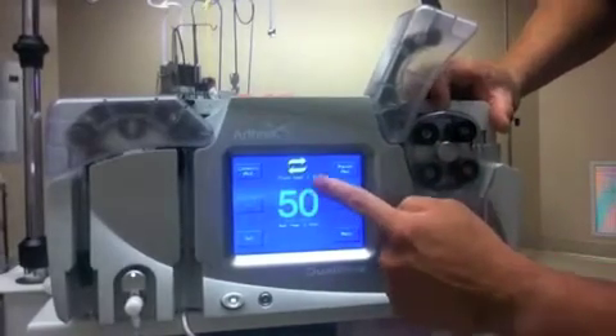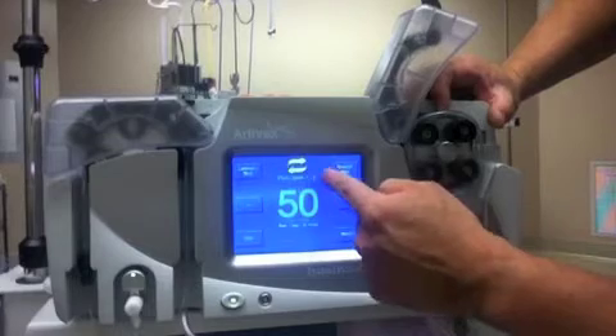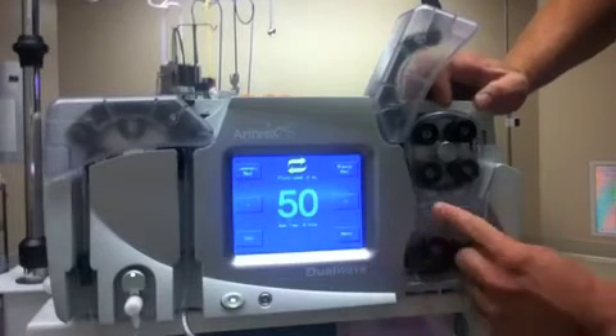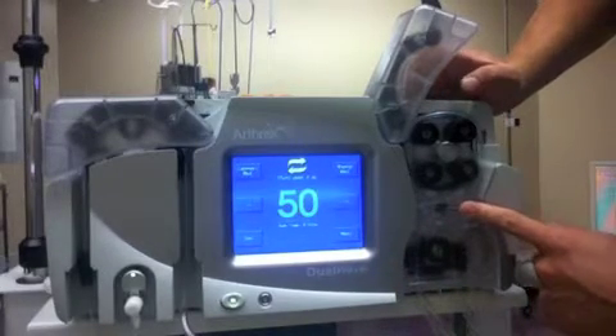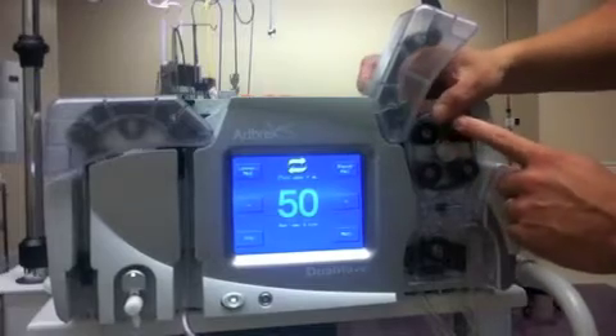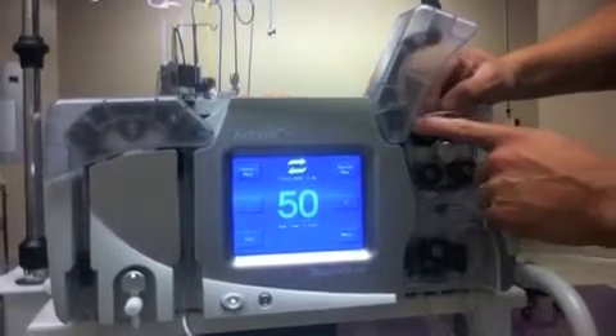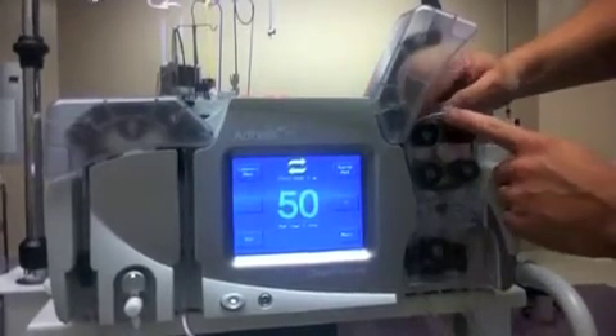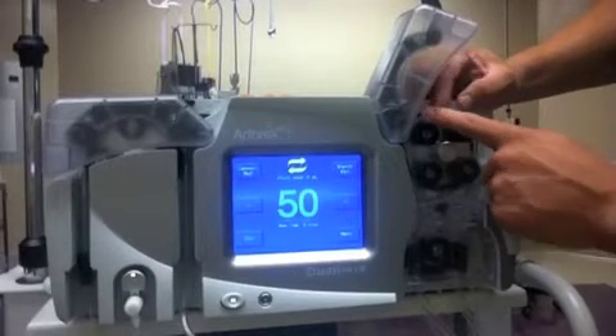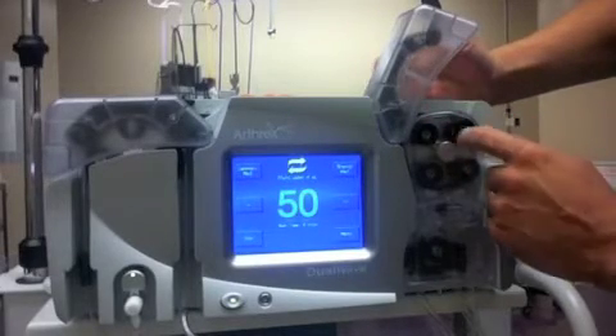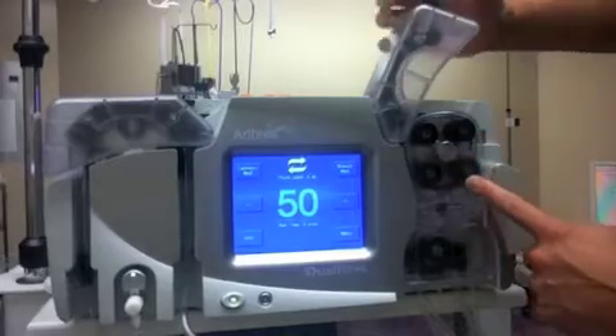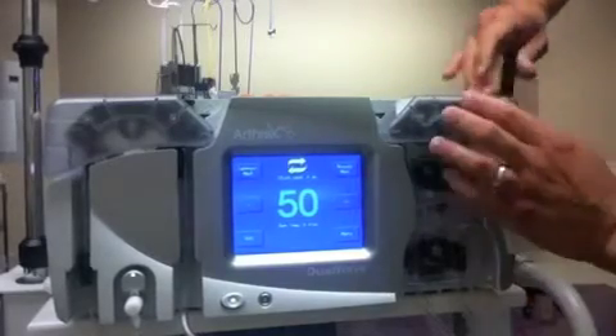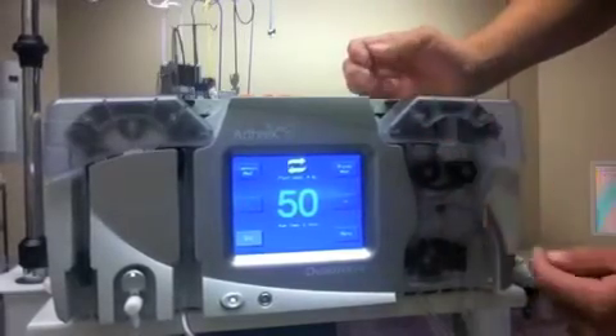You will see then the second arrow of 2 has been activated, indicating that it is properly installed. Just as with the inflow portion on the black rollers, you want to make sure that the tube is in the middle so as to not be spliced and to allow for proper circulation of fluid. Shut the door, and shut the lever.